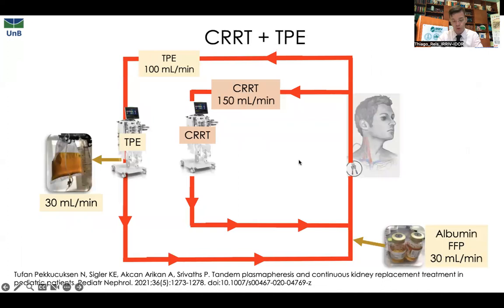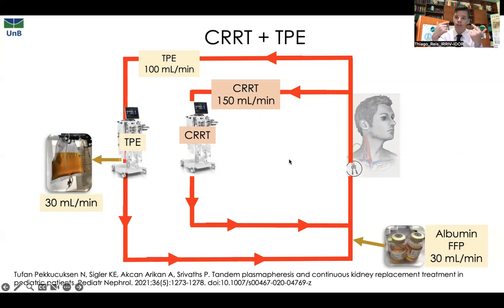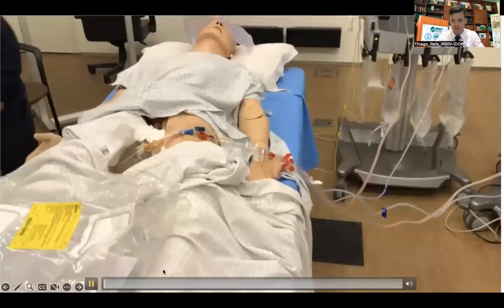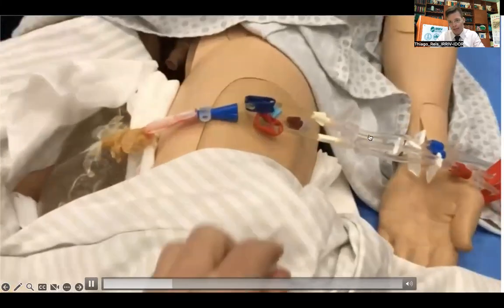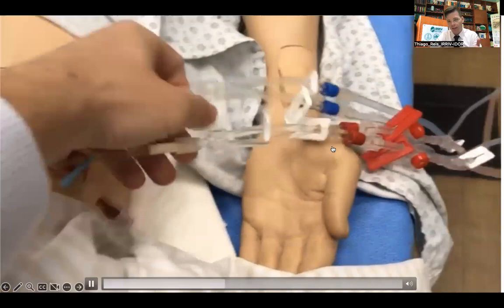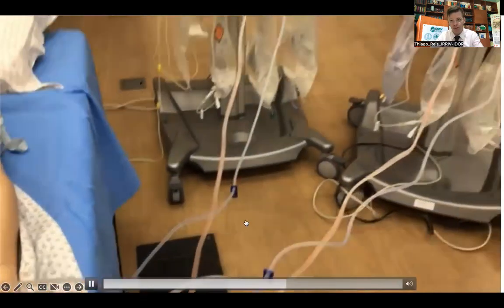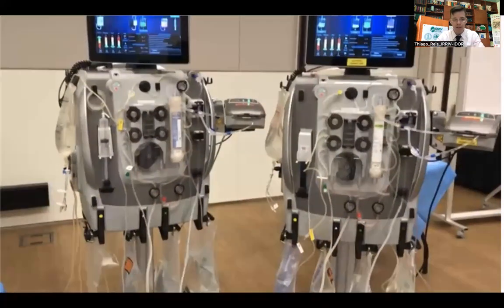It is also possible to apply plasmapheresis in parallel with CRRT. Using a Y-connector on both the inlet and outlet lines of a single catheter, you can run 150 mL/min for the CRRT circuit and 100 mL/min for the TPE circuit simultaneously. This avoids the need for an additional catheter and eliminates the need to stop CRRT to carry out TPE.